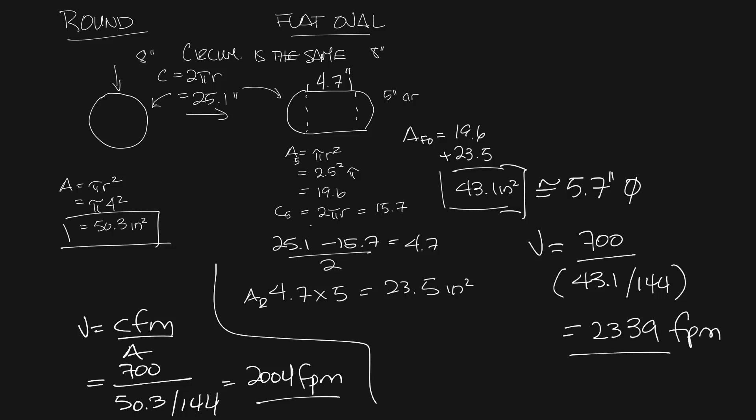So the air going through the flat oval is going about 300 feet per minute more than through the round. So depending on your application and what your airflow is, going from a round to a flat oval may cause issues in sound or pressure loss.